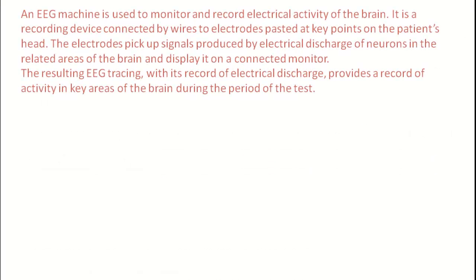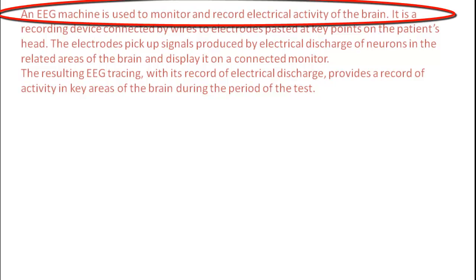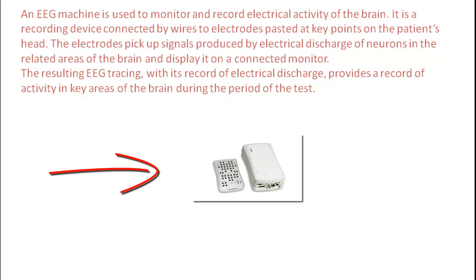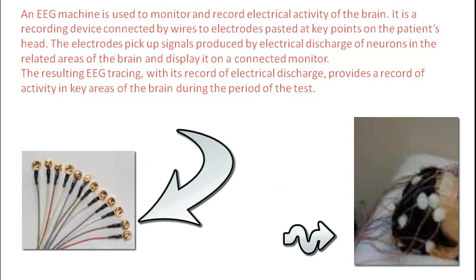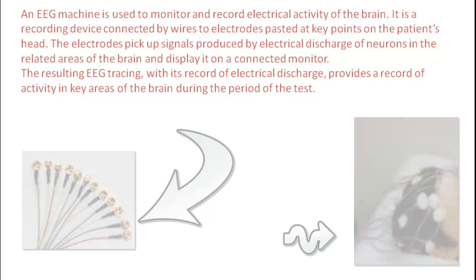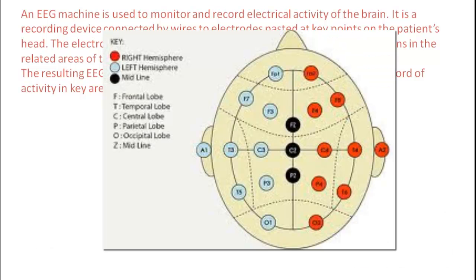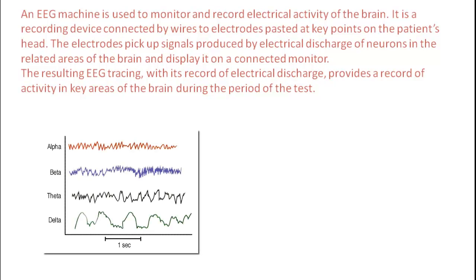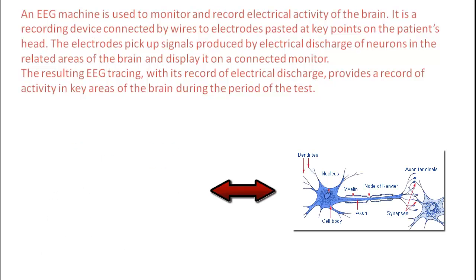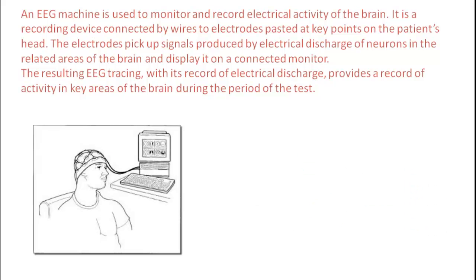First of all, if we recall back what we have learned earlier, the EEG machine is responsible for recording the brain waves. It monitors the electrical activity of the brain, and it has a normal PC with a monitor, keyboard, and basic components, and an amplifier connected to the PC. From the amplifier side, we have electrodes connected to the patient's head, connected according to the International 10-20 electrode placement system, or the Extended International 10-20 electrode placement system. These electrodes pick up the signal produced by the electrical discharges of the neurons in the related areas of the brain where they are connected, and display it on a connected monitor where the doctor can see and review it.